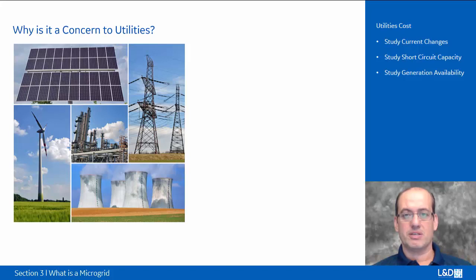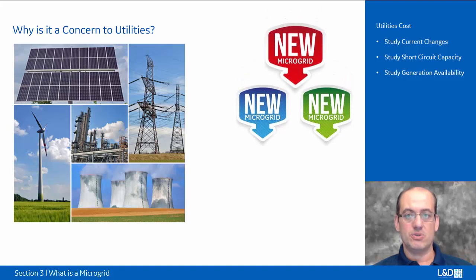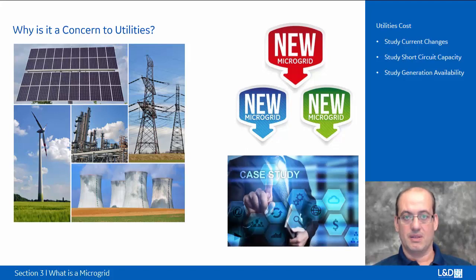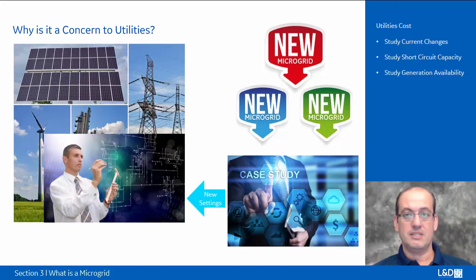If that microgrid is managed properly, if it maintains the requirements per the standards, whether we connect a 1 megawatt distributed generation or 10 megawatt distributed generation, if you increase the distributed generation, utilities have to restudy the system. They have to restudy it for fault current changes, short circuit capacity changes. They have to then take these studies and generate certain settings. These settings have to then be used to update their system. All of that, the case study, the settings, the updating of the system, translate into heavy cost for the utility.